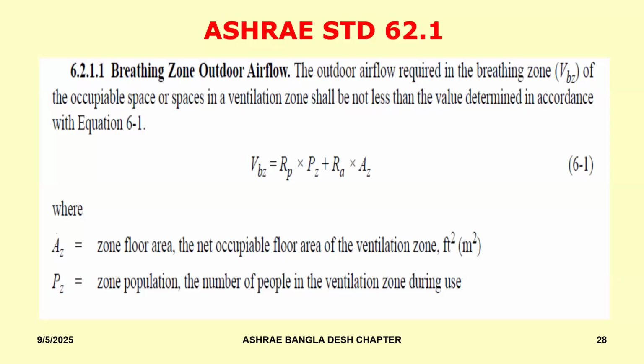So 62.1 provides you a kind of prescriptive number that says how much CFM per person you should have, coupled with CFM per square foot of the space. So that's why, if you see in this equation 6.1, the breathing zone outdoor airflow is a product of the number of people multiplied by the CFM per person, plus the area multiplied by CFM per square foot. Both of these together will give you the total zone outdoor airflow.